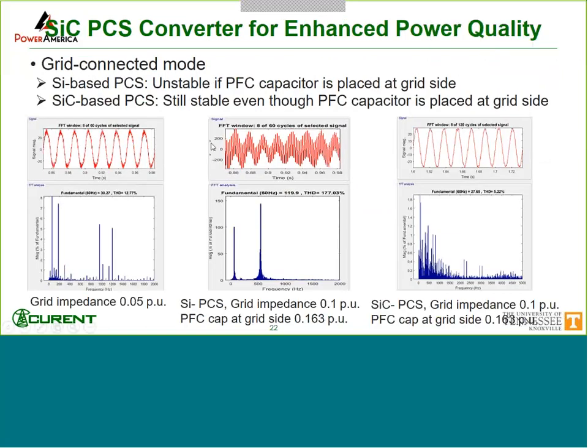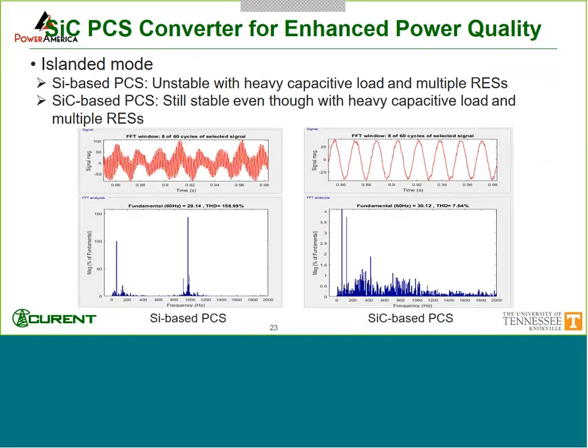So here is just some comparison, silicon-based case and silicon carbide-based case. One is switching at 1 kHz, the other is switching at 10 kHz with exactly the same load condition. And you will see that this is a grid connected mode, and the load is on the grid side. And you can see in one case, you could have the resonance. For the other case, the resonance disappears because of the higher control bandwidth available for silicon carbide. And this, of course, is for some fairly weak grid condition. It's about 10% impedance.